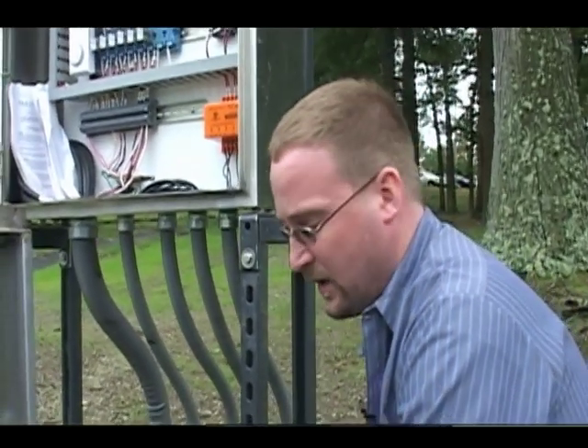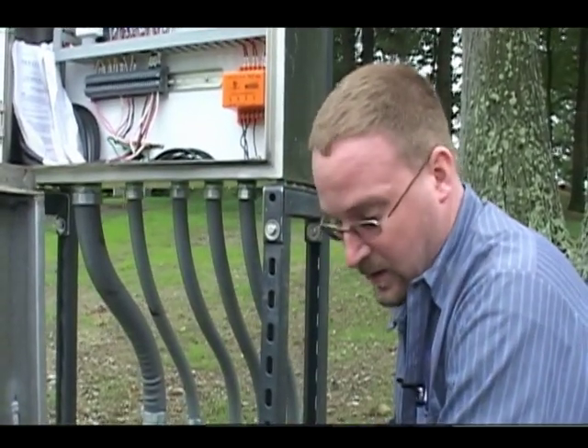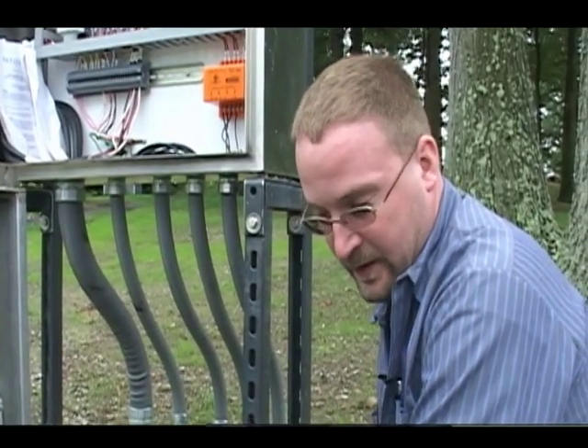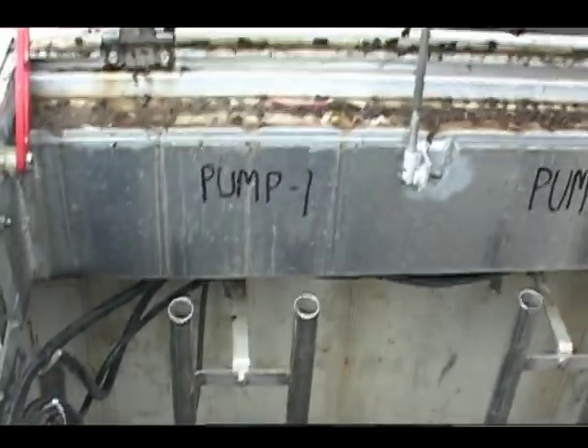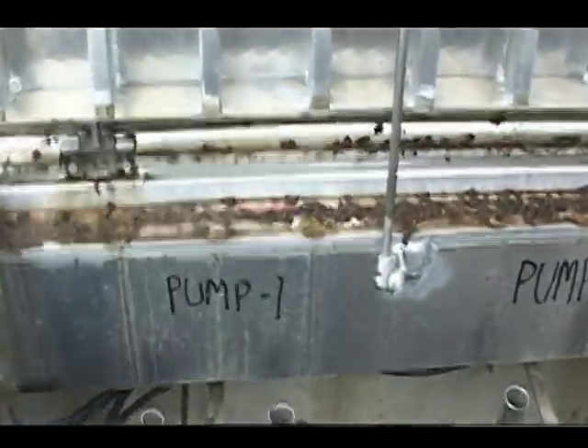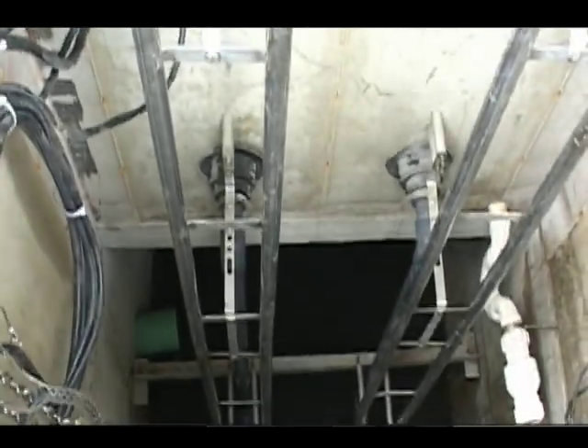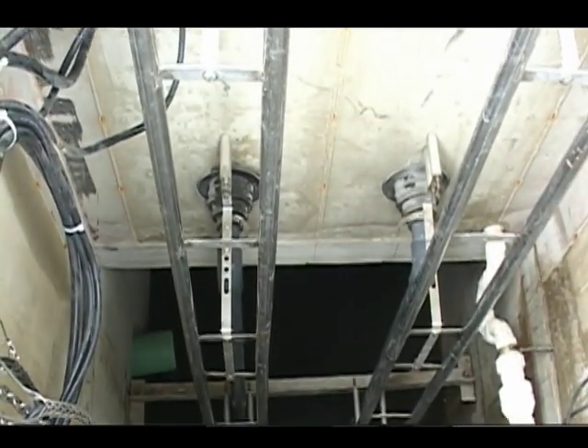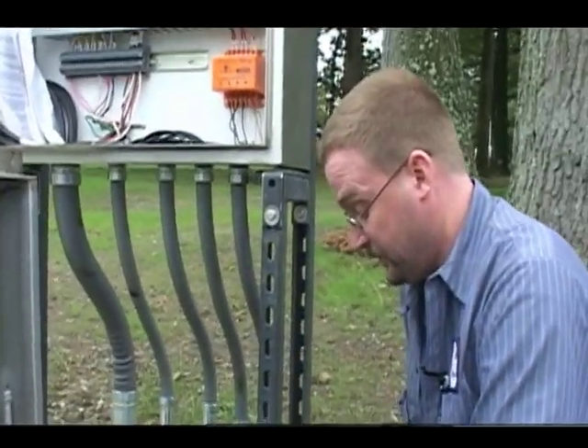The pump has seal sensor and motor sensors and a separate wire coming up through the conduit, and the motor sensors are also through the conduit. The TOPS rail system is mainly, if you look at the top here, just guideposts. And as you follow it down, the pump sits on what they call a pitless adapter for easy removal. Check valves come up with the pump, and you have a second set of check valves in the pump valve chamber. To lift the pumps up, use a crane or a chain fall and just pull it straight up, coming up slow just in case the pump gets hung up on anything as it comes up.